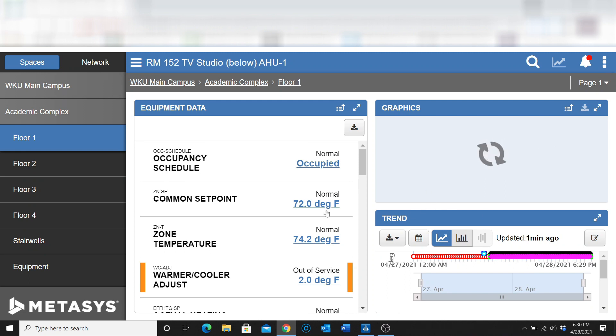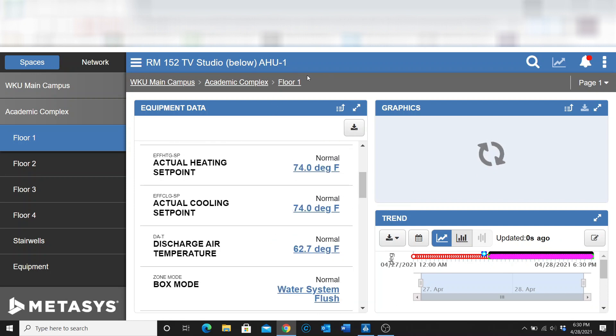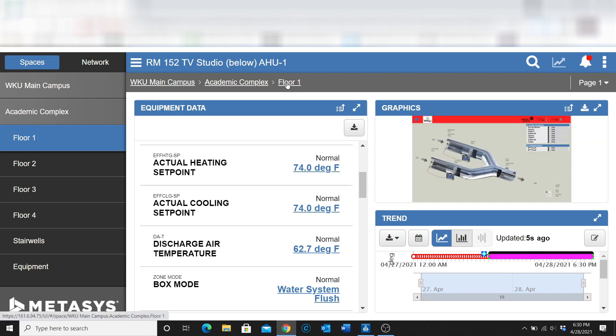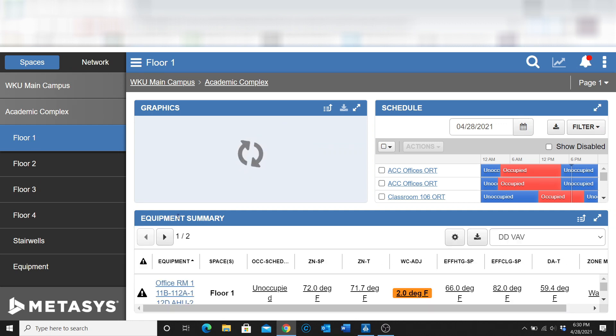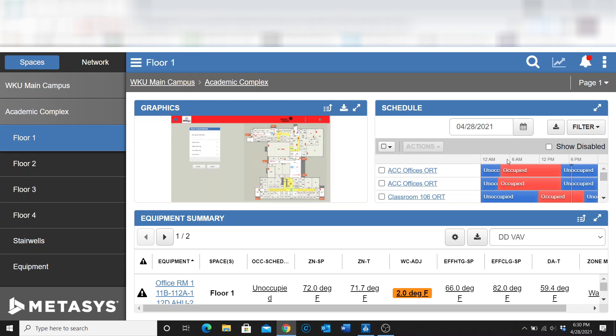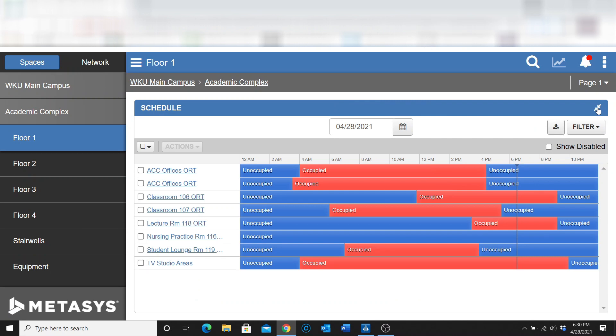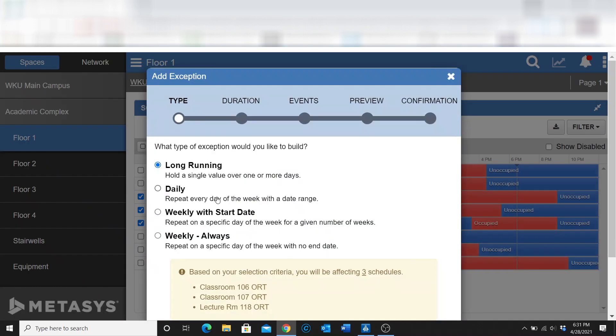I'm going to minimize that back to the graphic. Up here at the top I can actually go back to whichever area I want — whether that's the first floor or wherever. Clicking that brings me back to this graphic where I can go into my schedules. Another neat feature: I'm going to expand the schedules section out. Say I had a few rooms that are going to be used for some kind of special event — I can go through here, check each of those schedules, and apply or add an exception schedule to each of them from one single point.